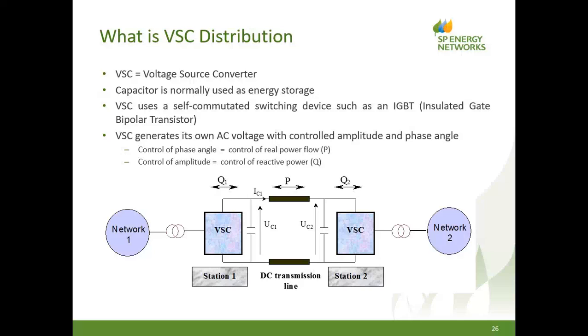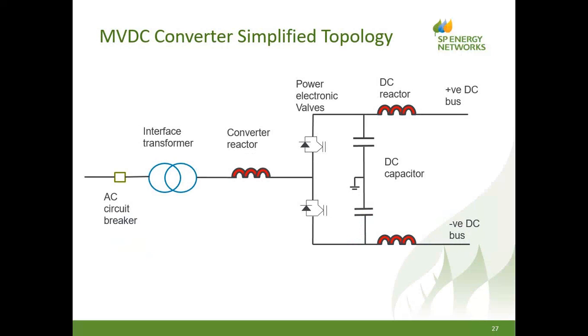So if we look at the converter in a little bit more detail in the next slide. This is a very simplified topology of a voltage source converter. So we connect to an AC circuit breaker, 33 kV breaker in the existing substation. We do require an interface transformer. So this transformer connects to the 33 kV AC network. The secondary of the transformer is essentially a free choice of the vendor of the equipment. His task is to achieve plus or minus 27 kV on the DC bus, so he can choose the secondary voltage of the transformer as he will.